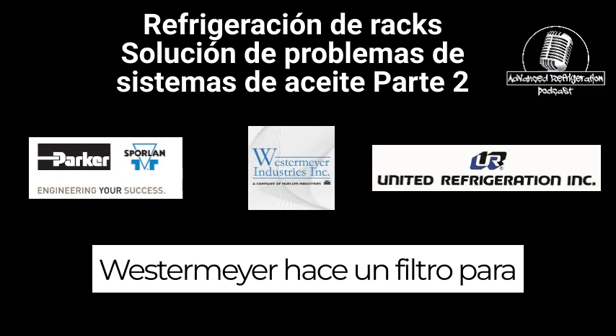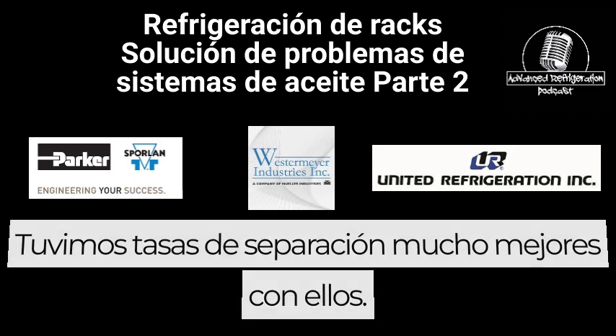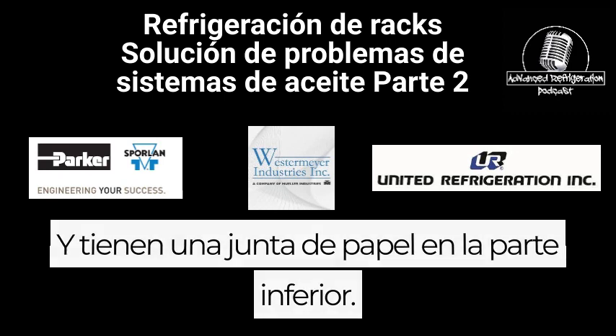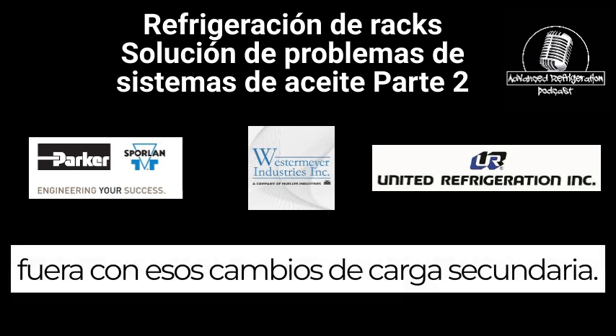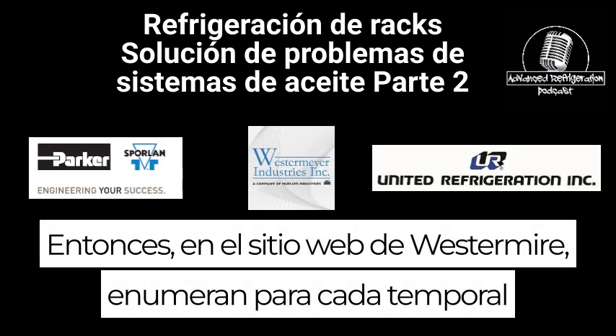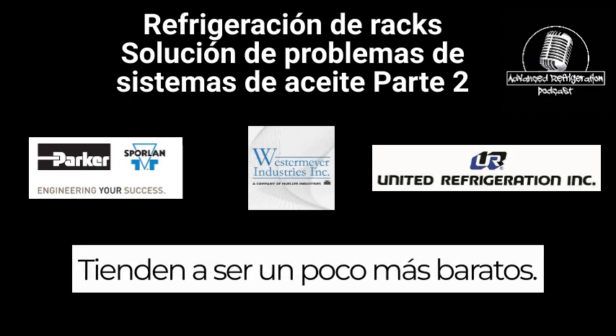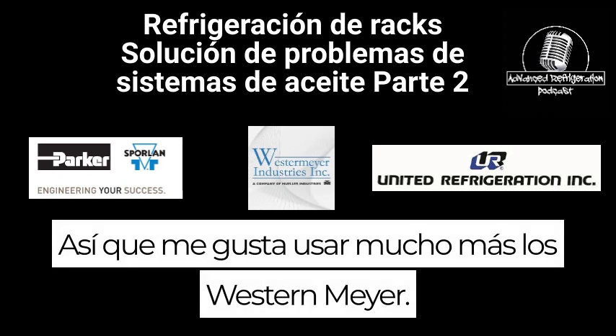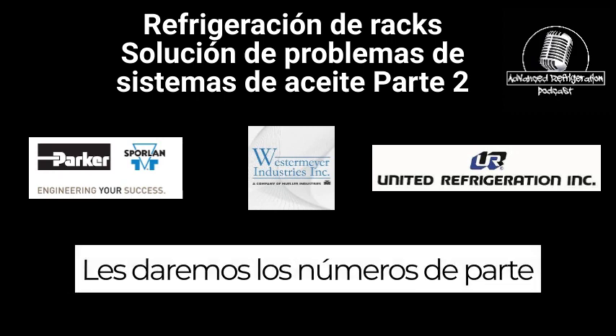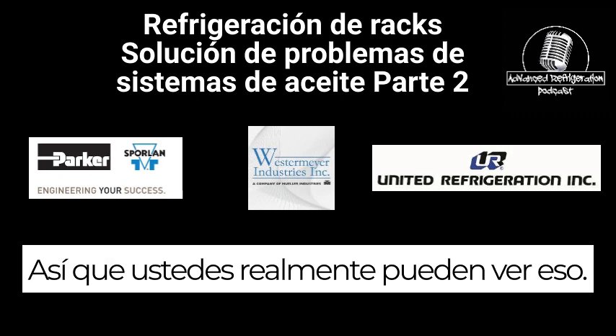Westermeyer makes a filter to replace every single Temprite filter. We started using them a year ago. We had way better separation rates with them, and they have a paper gasket at the bottom. The paper gasket does not blow out with those little sudden load changes. On Westermeyer's website, for each Temprite separator, they list a Westermeyer part number for it. They tend to be a little cheaper, and this way we're only carrying one brand of filters. So I like to use the Westermeyer ones a lot more. We'll get you guys the part numbers and put that on the Advanced Refrigeration Podcast Facebook group, so you guys can actually see that.